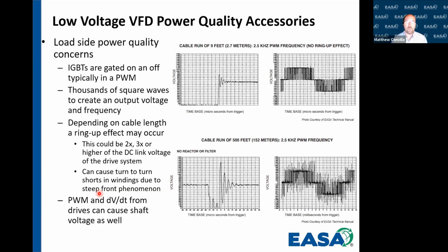When we think about our surge testers, we always have a time base that we set it at as well. So here's an example. Here's one of 9 feet, and you can see the voltage increases a little bit as compared to what it's supposed to be. If we look at one that's 500 feet at the same carrier frequency, now we have close to 700 volts, but we're over 200% of that. We're at about 1450 to 1500. So we've got that ringing up effect.